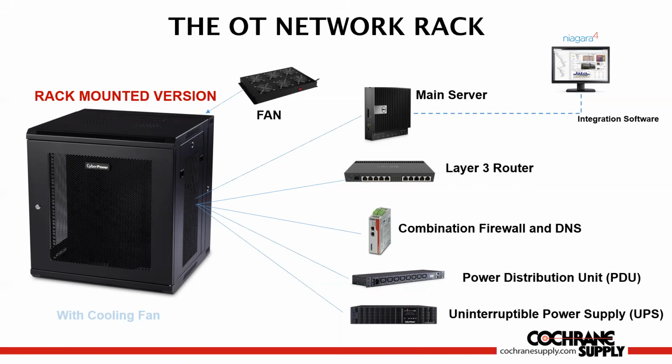So now you've got a cabinet with a bunch of components. You'll be able to specify a cabinet. The architect will know the weight and the size of the cabinet, so we'll know where this cabinet will fit. But it's important to show all this stuff on your drawings. I'm going to show you the drawings that we've been promoting to the engineering community called a systems integration drawing, right? It's a little more detailed than the typical systems architecture drawing you're used to putting in your controls drawings.